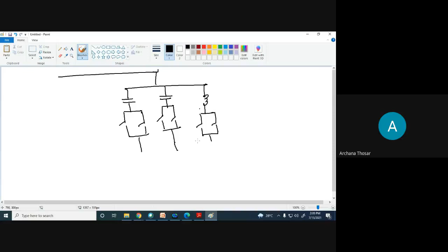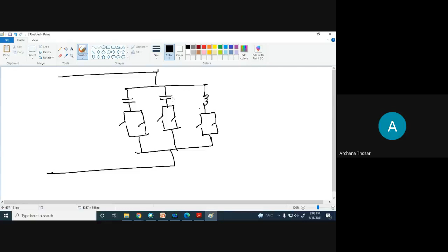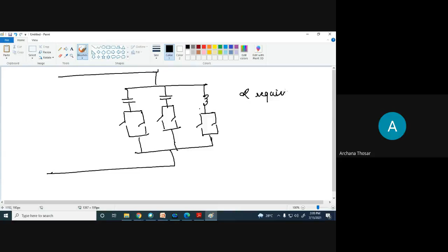These are the numbers. How many such branches of the thyristor switched capacitor should be there will be decided by the Q requirement of the line. So it will be connected in parallel, or in shunt, with the line. This will be the IQ flowing through it, this will be IC1, IC2, and this will be IL depending upon alpha. As you change alpha, the IL will go on changing. So this is the thyristor switched capacitor, thyristor controlled reactor.